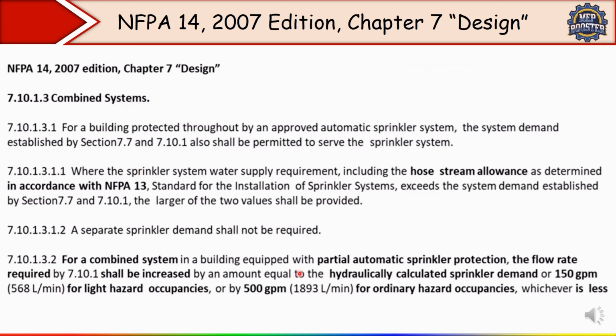You can see here the requirement is given clearly, okay. See, for partial automatic sprinkler protection, the flow rate shall be increased by an amount equal to the hydraulically calculated sprinkler demand or 150 GPM for light hazard. So you can add an additional 150 GPM, or otherwise do the hydraulic calculation separately for that sprinkler, and whatever flow you get, you need to consider that. This is for light hazard. For ordinary hazard, 500. Okay. So in this way, you will get the total demand for the combined system. Hope all of you understood about this.